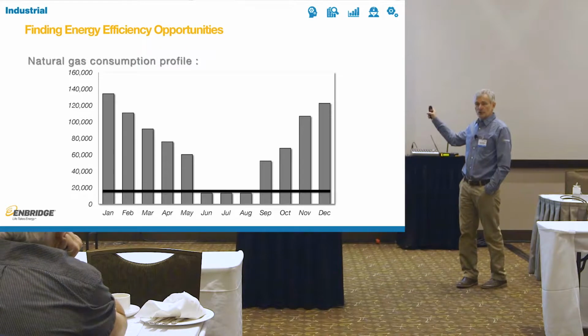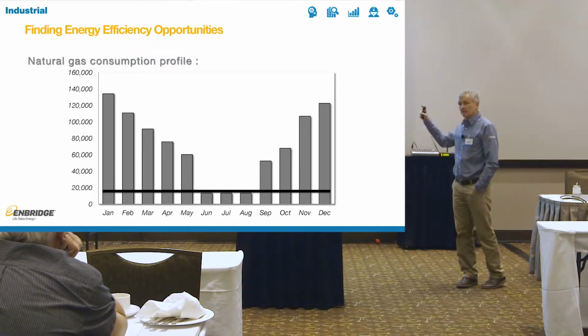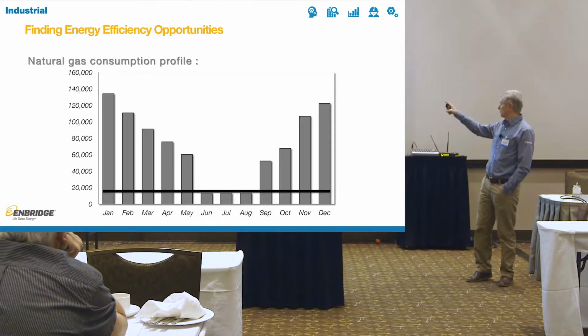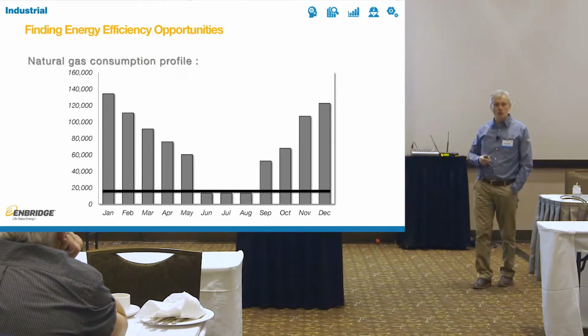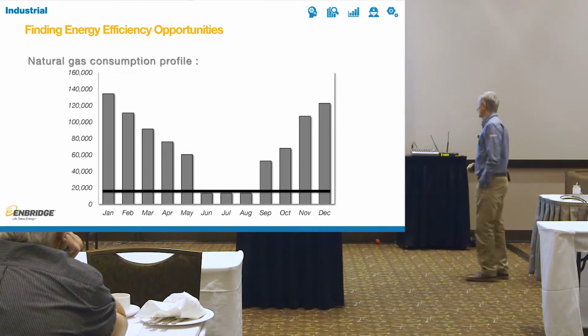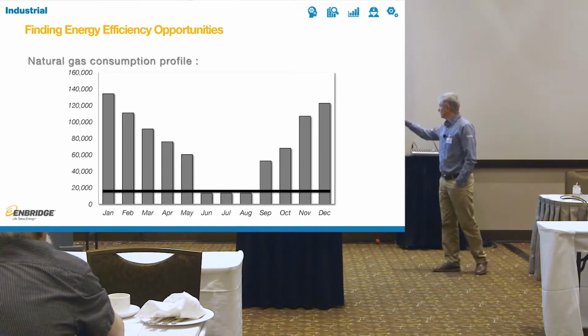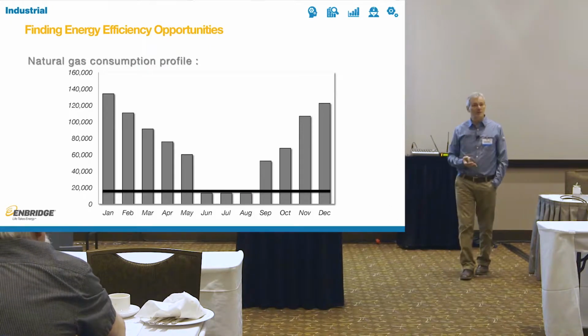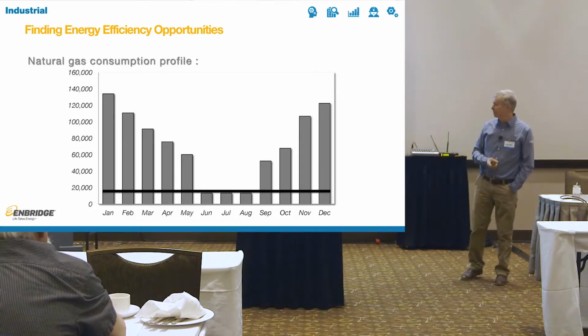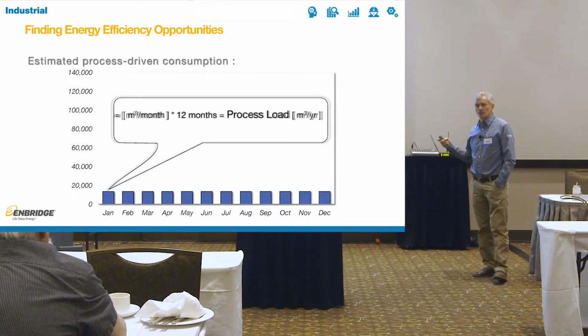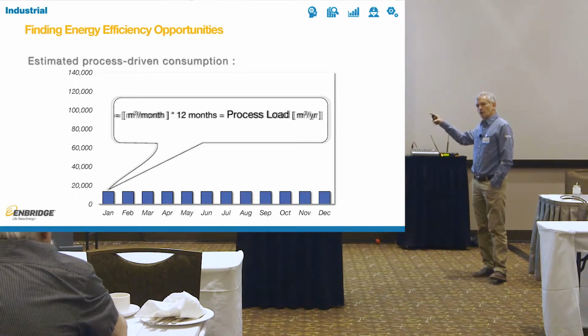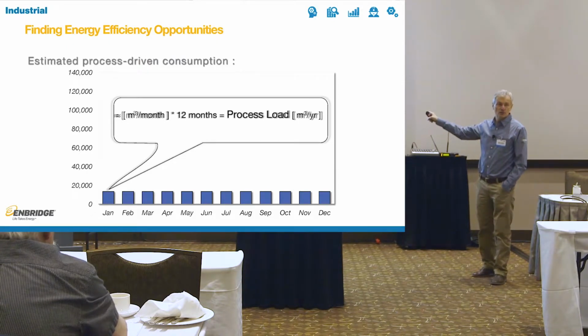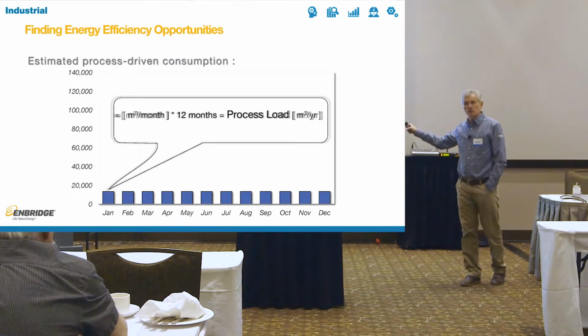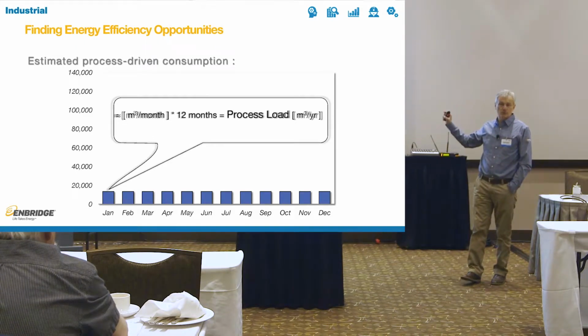Natural gas consumption, if you draw it out month by month, should look something like this. Some of you will have a flatter profile, some of you will have more of a U profile, depending on your loads, but it will look something like this. So if we eliminate the bottom part, if we say June, July, August, there is absolutely no way you're actually using any heat for seasonality purposes, then what you are left with is your process load. This is your process load. So if this is representative of your facility, this big U shape, and you're left with this process load, don't be looking at the process as your number one opportunity to save energy, because you'll be using a lot of effort and money without much payback.